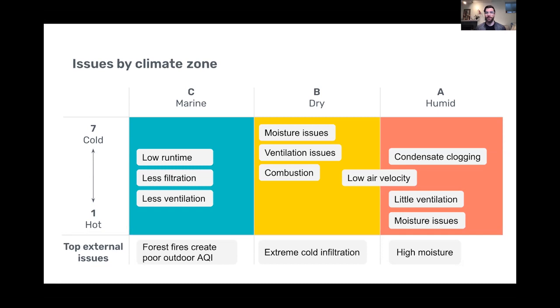And then finally, climate zone A, which we've identified as being the majority of the population and IAQ issues we see, is one of the most difficult. And what you see, first of all, is that the air conditioners that are running are pulling some of the moisture out. They're acting as dehumidifiers. And so that condensate management becomes really important. You get clogging of the ability to pull that moisture out, which leads to flooding of the equipment, shutting off emergency safety switches, triggering, leading to a no cooling call.